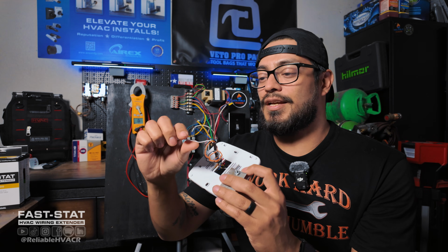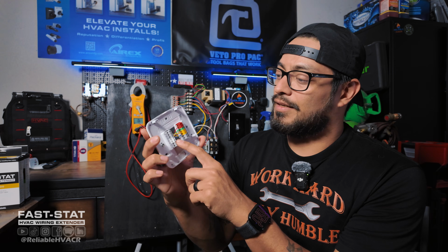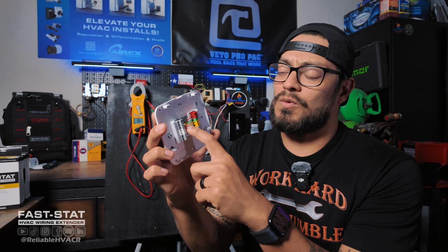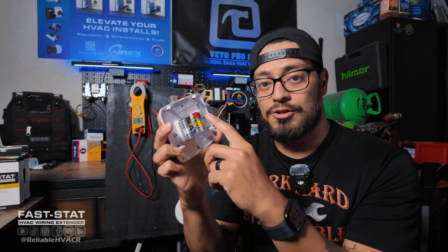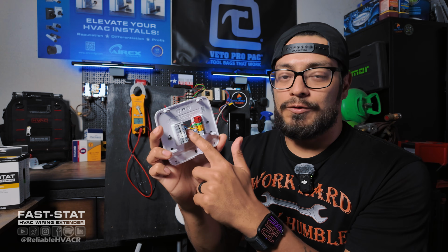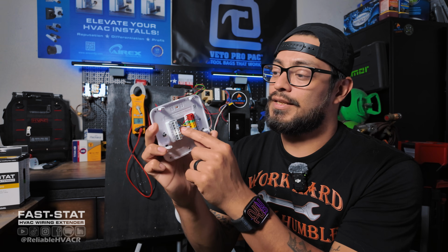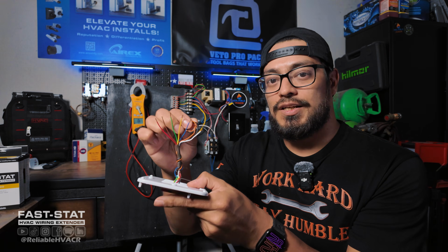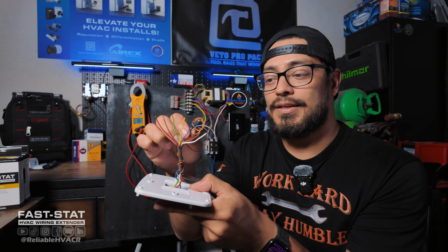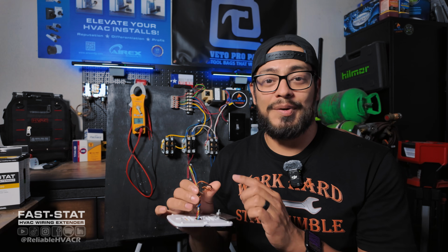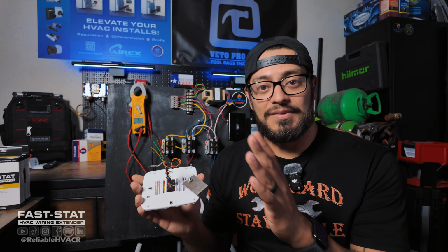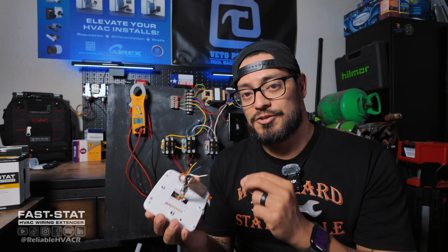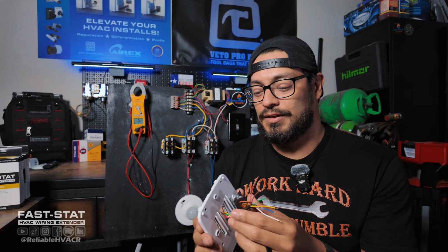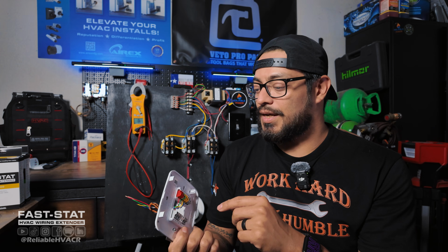So typically, let's say this white W1 wire is no good. It's either shorted or broken. You would remove that one completely, cut it off, take it off this terminal right here. And if you see any extra wires, it could be like this orange or black, connect that there and do the same thing on that indoor unit or wherever that thermostat wire lands. Now, that's best case scenario. If you find that, you're lucky. Somebody actually gave you some extra wiring there and some slack, hopefully. So that's one way to do that.